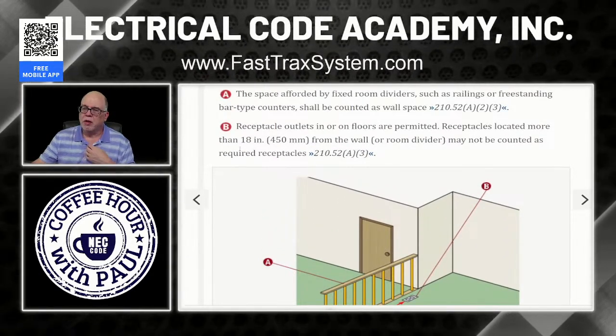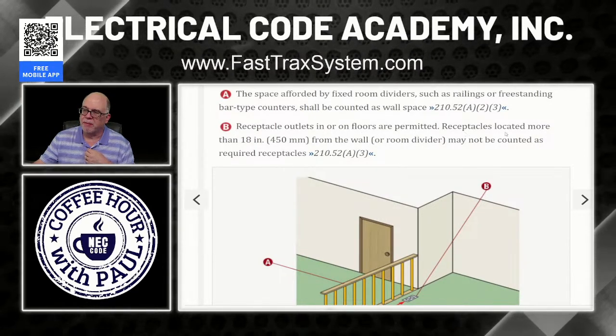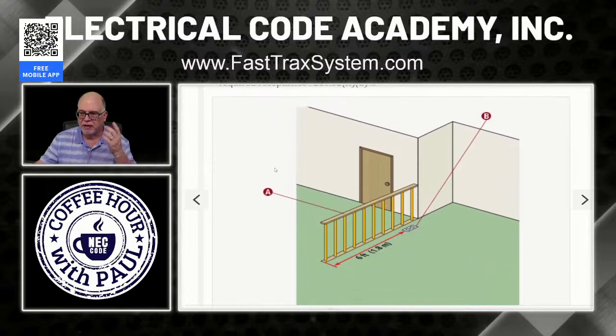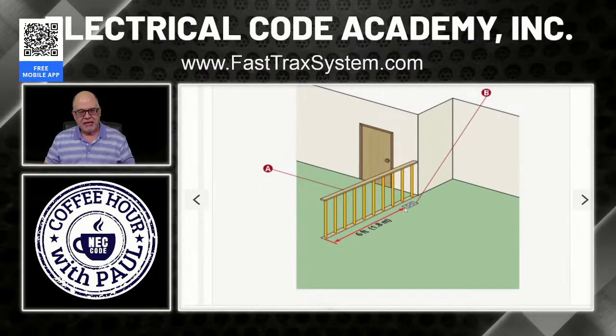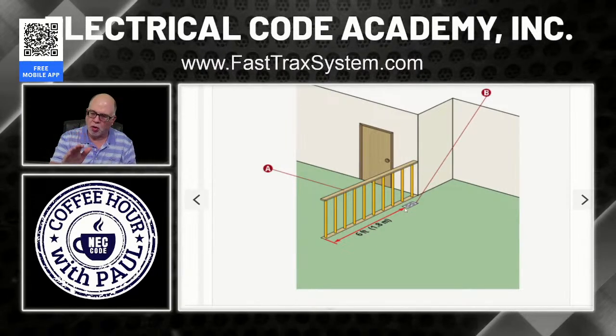Now, the receptacle outlets in or on the floor are permitted. Receptacles located more than 18 inches from the wall or room divider may not be counted as the required receptacle. Okay, that is in 210.52(A)(3). So let's talk about that for a second. Floor receptacles. Can I have floor receptacles instead of the receptacles that are actually in the wall? Absolutely, as long as they're located within 18 inches of the wall.